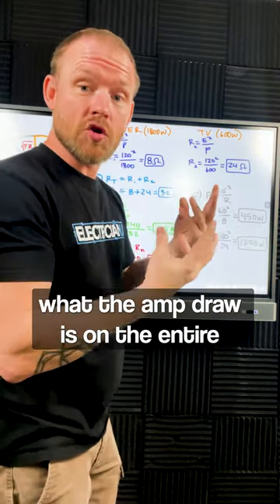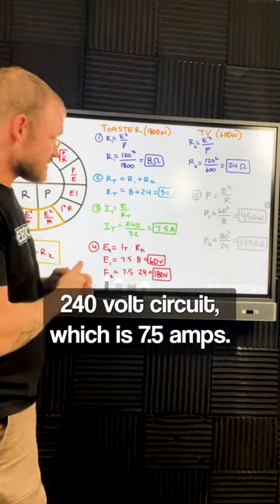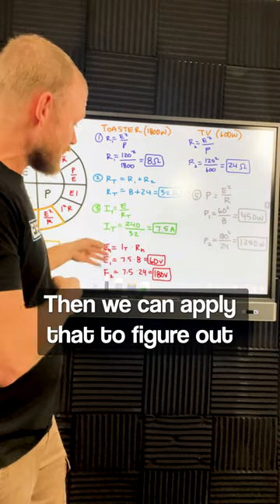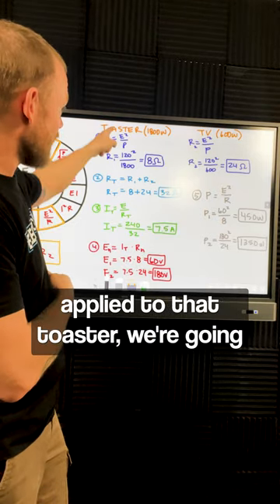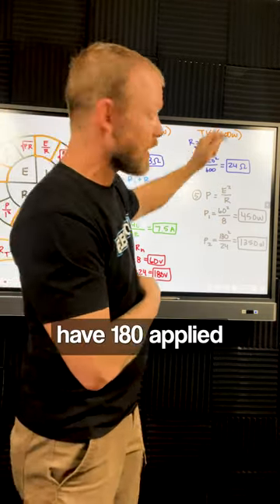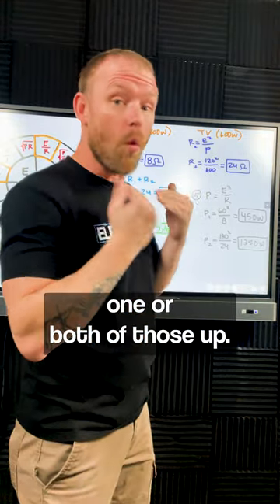Then we can figure out what the amp draw is on the entire 240 volt circuit, which is 7.5 amps. We can apply that to figure out what the voltage for each load is. In this situation, we're going to have 60 volts applied to that toaster and 180 volts applied to the TV. That's going to burn one or both of those up.